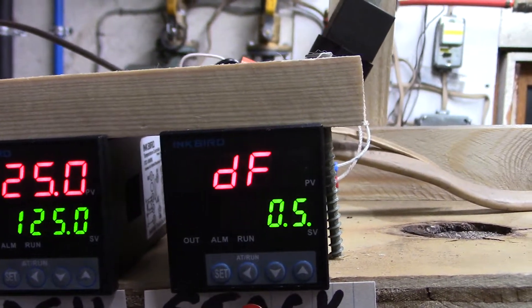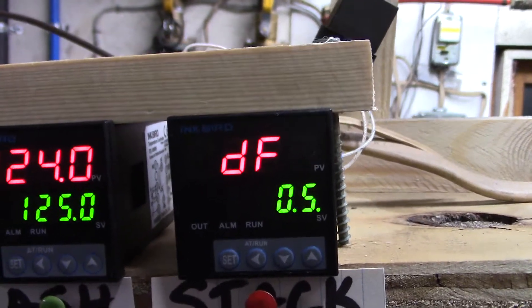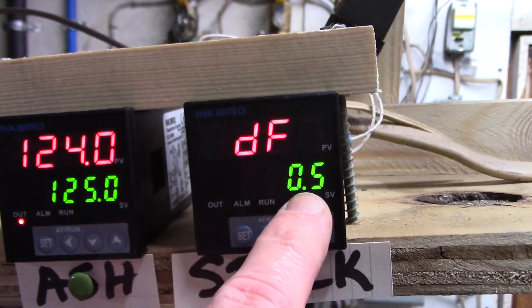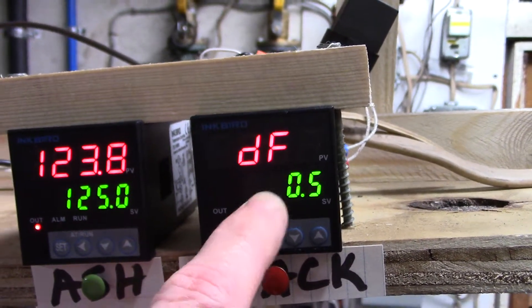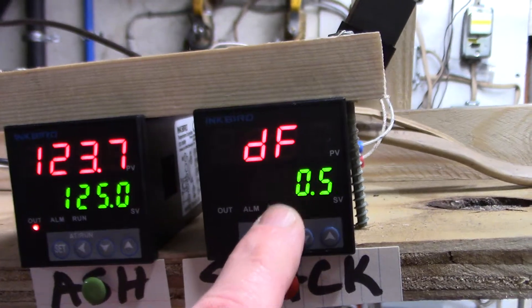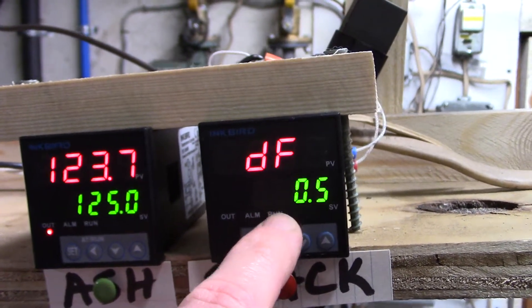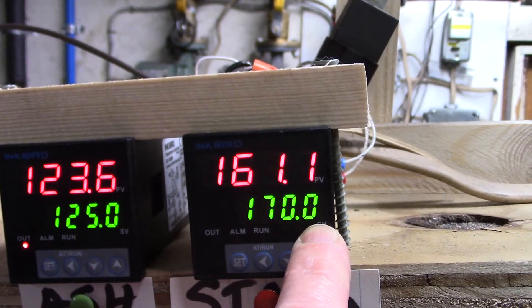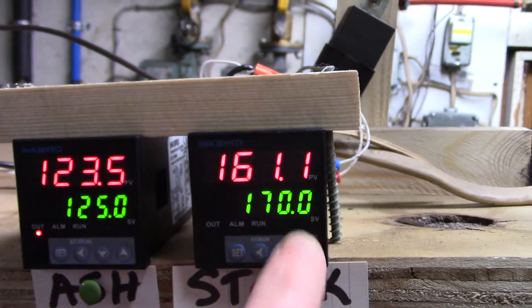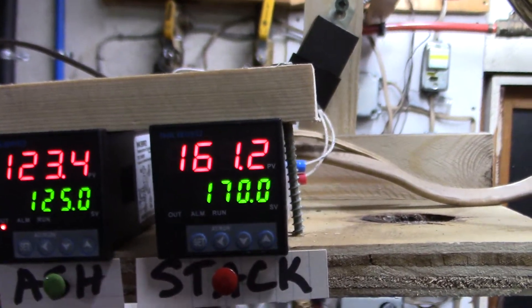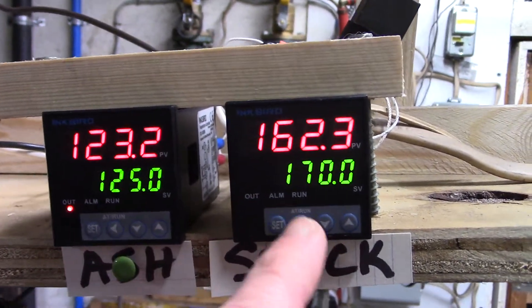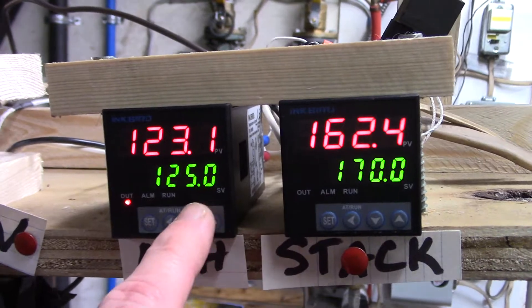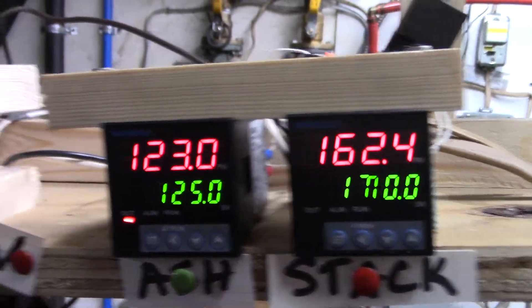We have this set at 0.5. From the factory they come at 0.3, and that is the hysteresis effectively, it's the differential. It's like how far it will go before it actually does anything. So with it at 0.5 and having a set point at 170 degrees, really it'll activate when it gets to 170.5 degrees.